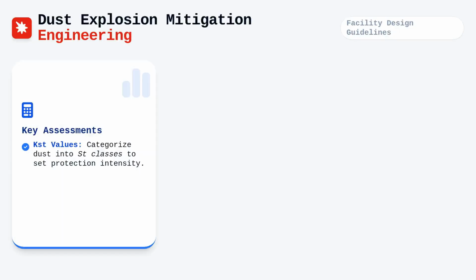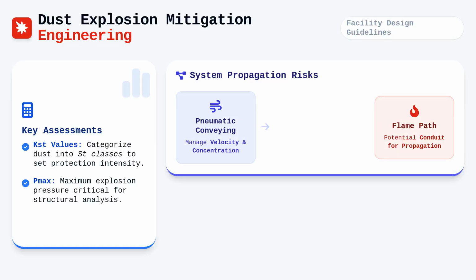When engineers design systems for facilities handling powders, they must prioritize the assessment of KST values and maximum explosion pressure, also known as Pmax. A KST value categorizes the dust into St classes, which dictate the necessary intensity of downstream protection like venting or suppression. If you are designing pneumatic conveying systems, you are essentially creating a potential conduit for flame propagation if the dust velocity and concentration are not strictly managed.